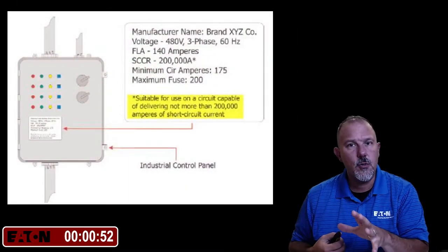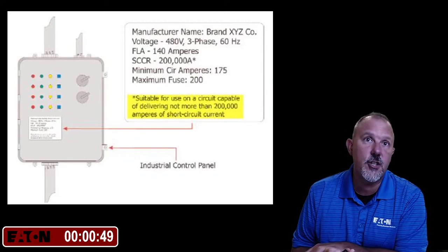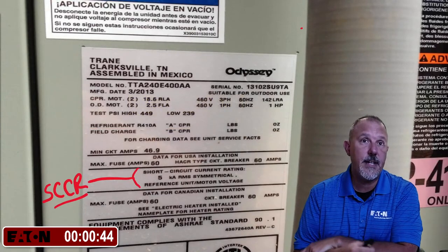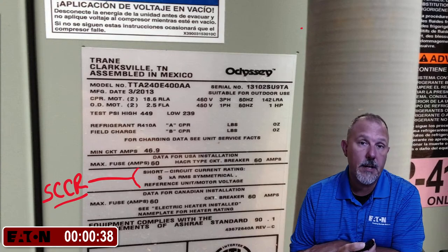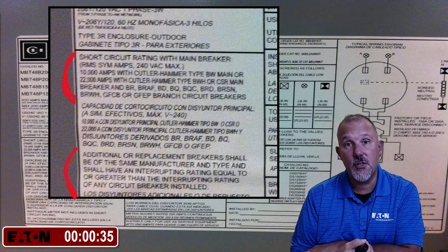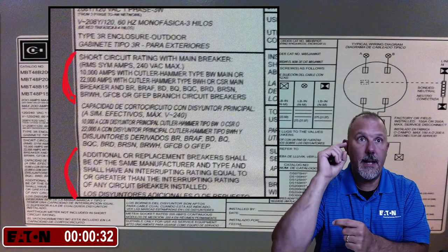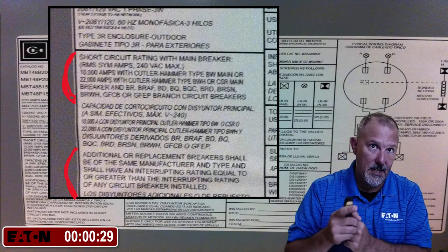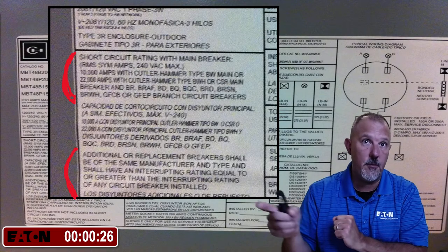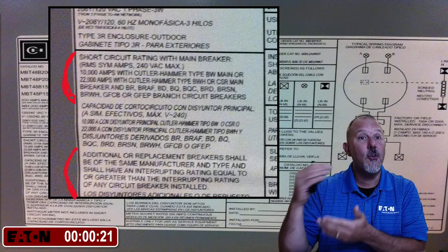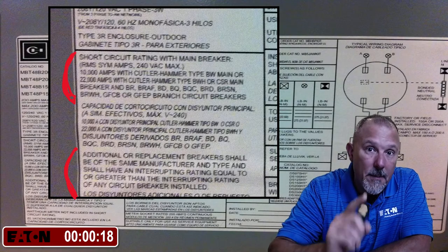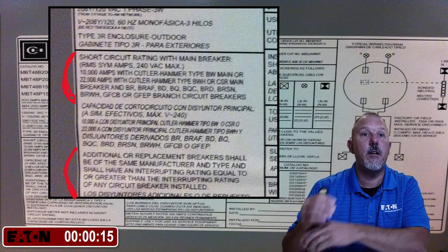Equipment will have a short circuit current rating marked on it. In one example, the SCCR is 200,000 amps. In this HVAC case, the short circuit current rating is 5,000 amps and it specifies the maximum fuse size. In another label, the rating goes to 10,000 amps with a Type BW main, or 22,000 amps if a BWH type is used — you get the higher rating because of the overcurrent device's current-limiting capabilities protecting the downstream equipment.